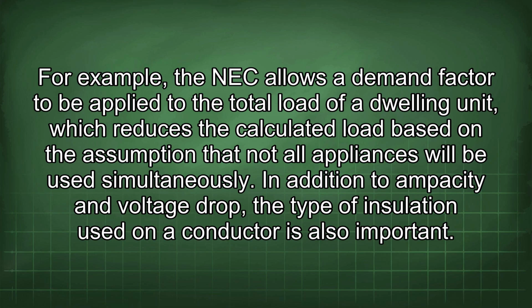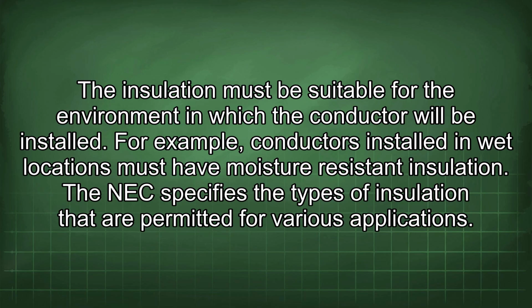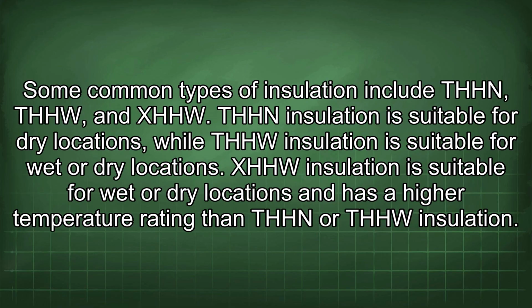In addition to ampacity and voltage drop, the type of insulation used on a conductor is also important. The insulation must be suitable for the environment in which the conductor will be installed. For example, conductors installed in wet locations must have moisture-resistant insulation. The NEC specifies the types of insulation that are permitted for various applications. Some common types of insulation include THHN, THHW, and XHHW. THHN insulation is suitable for dry locations, while THHW insulation is suitable for wet or dry locations. XHHW insulation is suitable for wet or dry locations and has a higher temperature rating than THHN or THHW insulation.